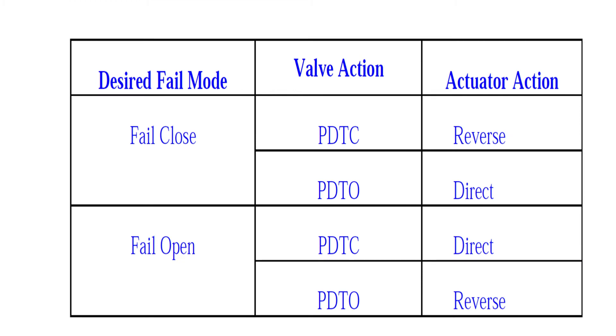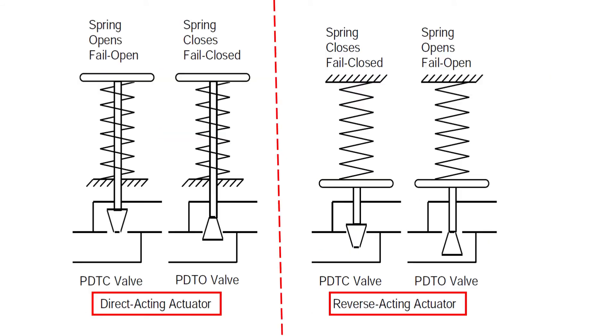This chart allows us to decide fail-safe conditions with respect to actuator action. We have already discussed the fail-safe modes — fail safe open, fail safe close, and lock in last position. From this chart you can clearly see that depending on your requirement: if your requirement is fail safe close, you can choose either a direct or reverse acting actuator; if the fail mode is fail safe open, you again have a choice of selecting direct or reverse acting actuator.